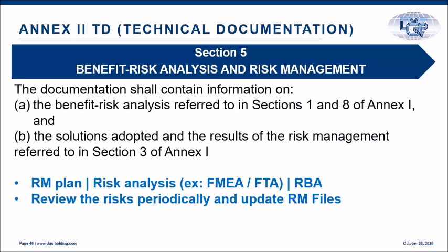Section 5 of the technical file, risk management and the risk benefit analysis. You need to provide the complete risk management file, including the risk benefit analysis, in compliance with ISO 14971:2012. Specific focus on Annex ZA, ZB, ZC, whichever is applicable depending on the nature of your product. That needs to be demonstrated, and the complete file needs to be provided, including verification and validation of risk mitigation activities. So the complete risk management file demonstrating compliance to 14971 needs to be provided.